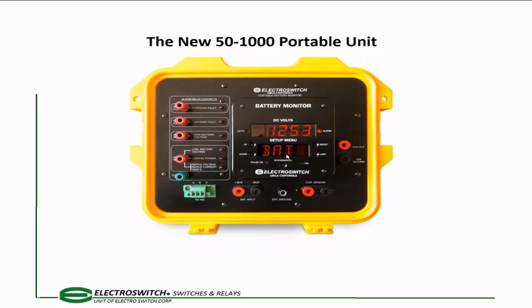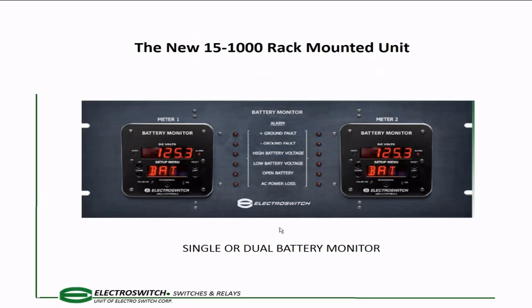So this unit, the panel mount, rack mounted, or portable unit, as the standard battery monitor, comes with DNP, Modbus, or 4-20, which is a step above our last versions of battery monitors. This is a rack-mounted version, and this is showing a dual battery voltage system, but it can be single or dual battery voltage. Once again, you have your LEDs showing positive, negative ground fault, high, low battery voltage, open battery, and AC power loss.